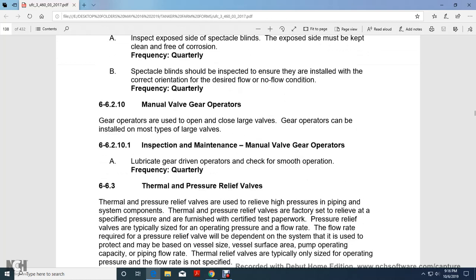Gear operators are used to open and close large valves. Gear operators can be installed on most types of large valves. For inspection and maintenance of manual valve gear operators, lubricate gear driven operators and check for smooth operation quarterly.